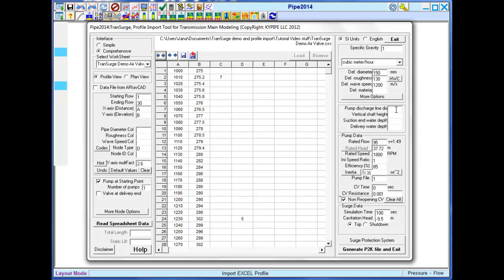Some advanced pump data is available here, but this last field, delivery water depth, is used for the pipeline discharge when a vessel has a positive head. If the discharge is to atmospheric pressure, just leave this blank.